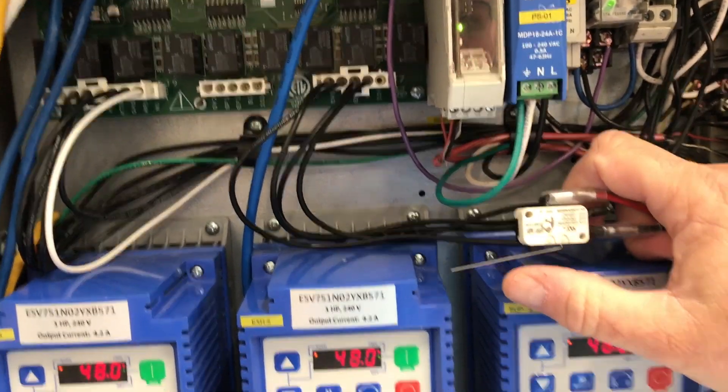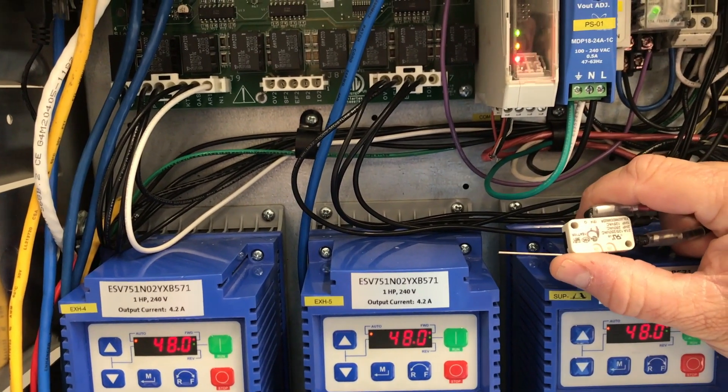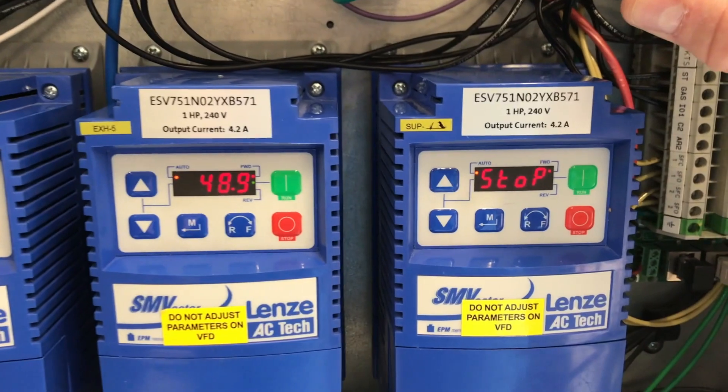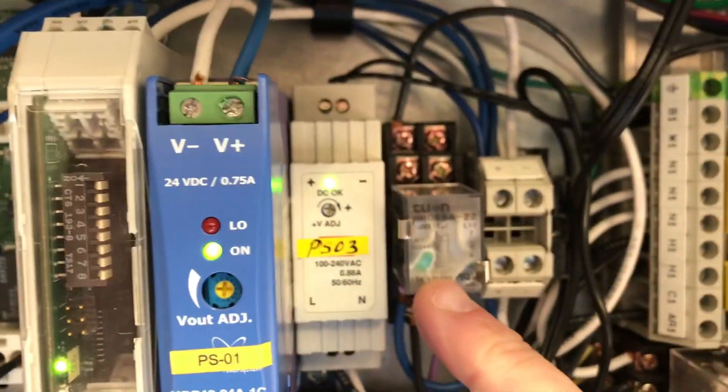So if the Ansul system gets triggered, the Ansul system is going to operate the microswitch. What's going to happen is your supply VFD will go to stop, my exhaust VFDs will ramp up to full speed, and my lighting relay will be de-energized, turning off my hood lights.